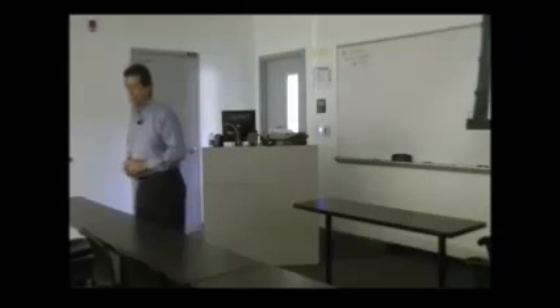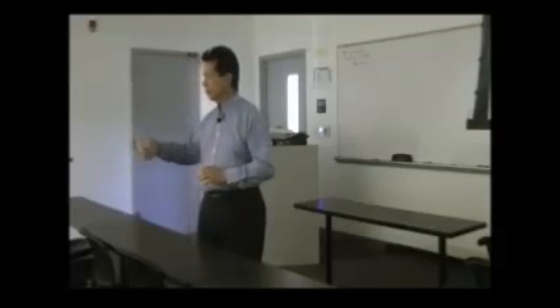Operator proficiency is another one: training and experience, what to look for. As you walk through your equipment and areas, having that keen eye to identify potential problems. When I walked through the older central plant, I noticed a lot of J boxes without covers, with wires sticking out. If nobody fiddles with the wires, it's probably okay, but over time, if that continues, it may cause problems within that central plant, like wire nuts that have fallen off, leaving only leads twisted together.